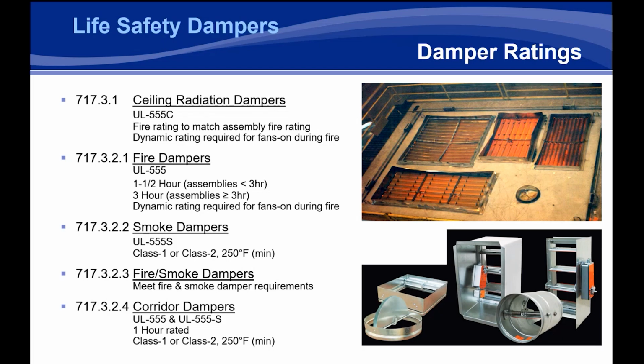So basically, a dynamic system is a system where the fans will be running during a fire, whether they're intended to or not. This language in the International Building Code actually stemmed from a bit of a loophole in the mechanical code. So the International Building Code and the International Mechanical Code are both developed by the ICC, the International Code Council.